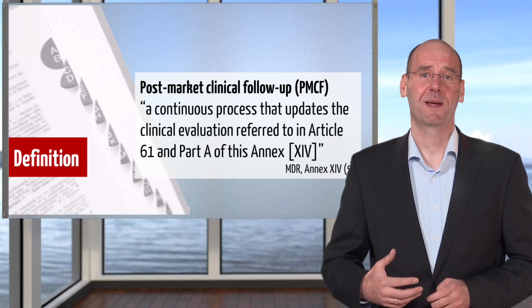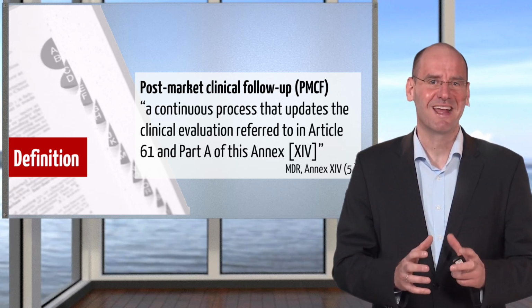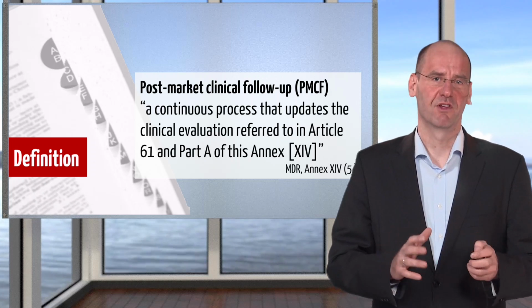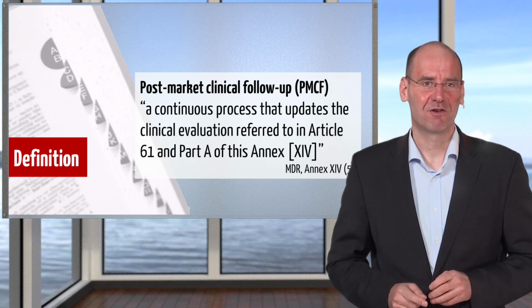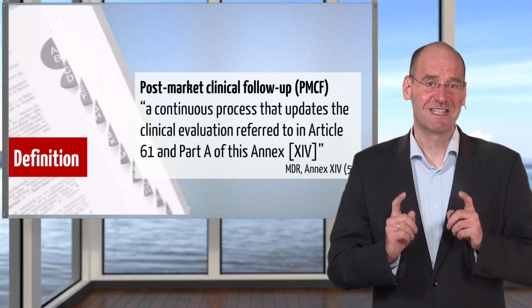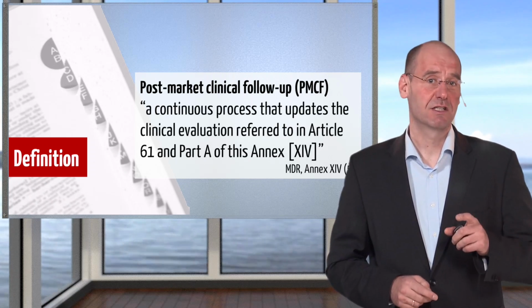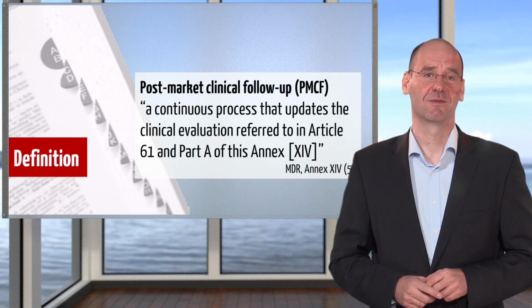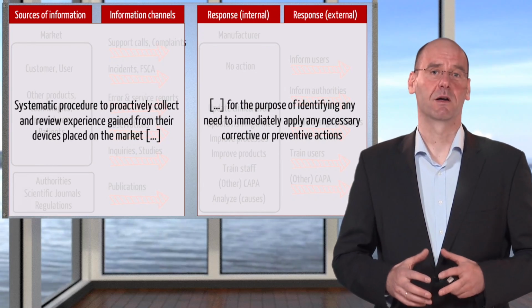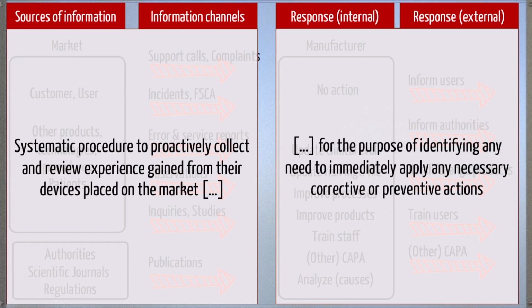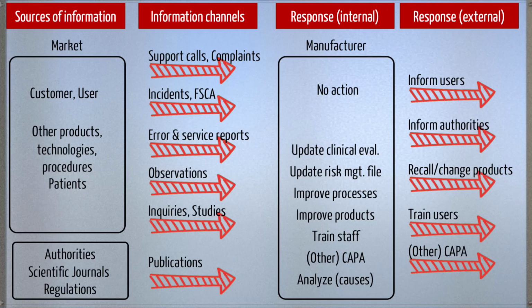The requirements with respect to clinical evaluation also became very specific and much about the MEDDEV 2.7/1 revision 4. Don't underestimate the efforts to come up with the PMCF plan, to continuously collect and evaluate data and to keep not only the clinical evaluation up to date. Even a little broader is the scope of the post-market surveillance. Also here, data have to be systematically and continuously collected, updated and evaluated. But the outcome of this activity is not just an updated clinical evaluation, but any other measure such as process improvements, medical device reporting, product recalls and other corrective and preventive actions.